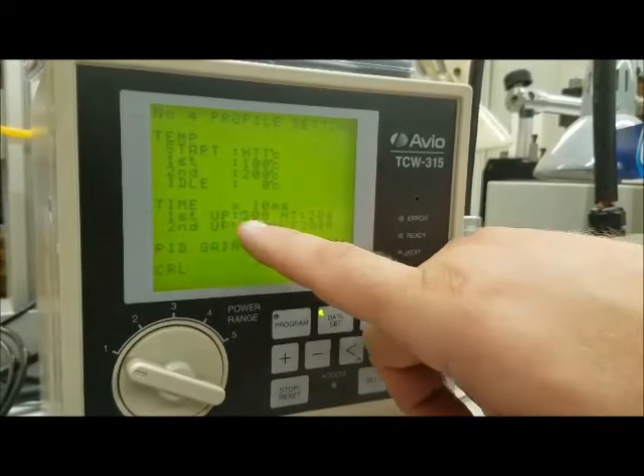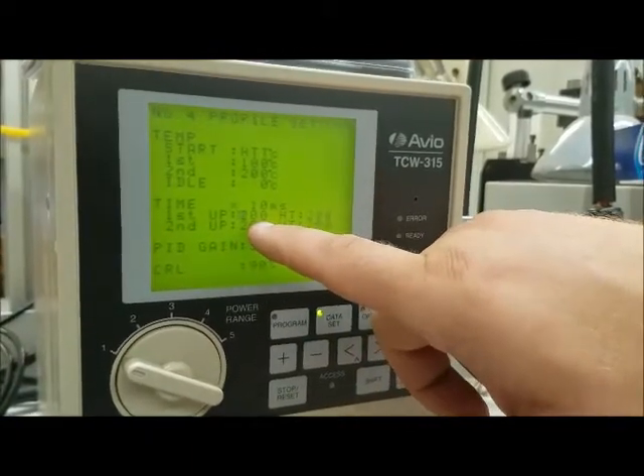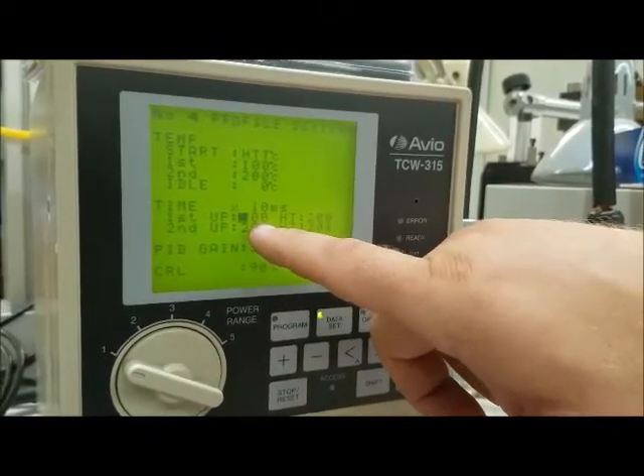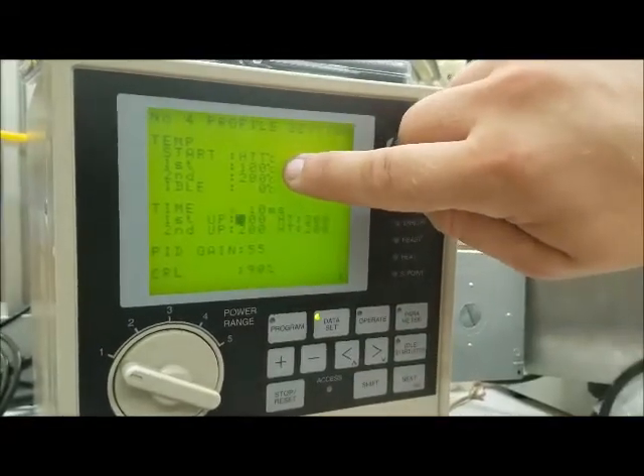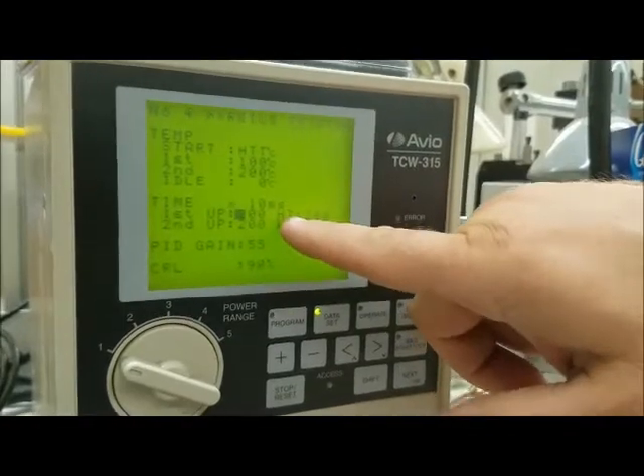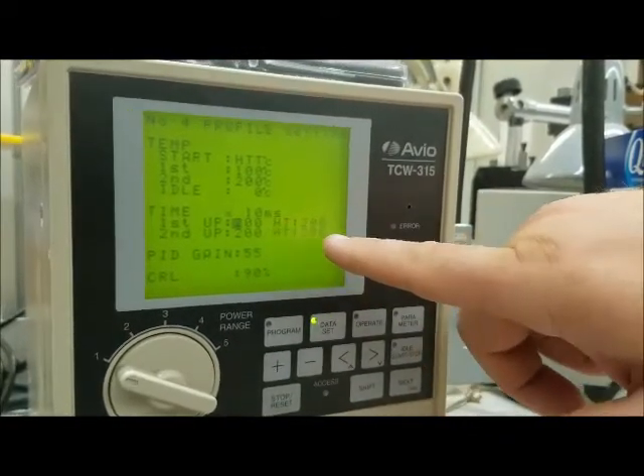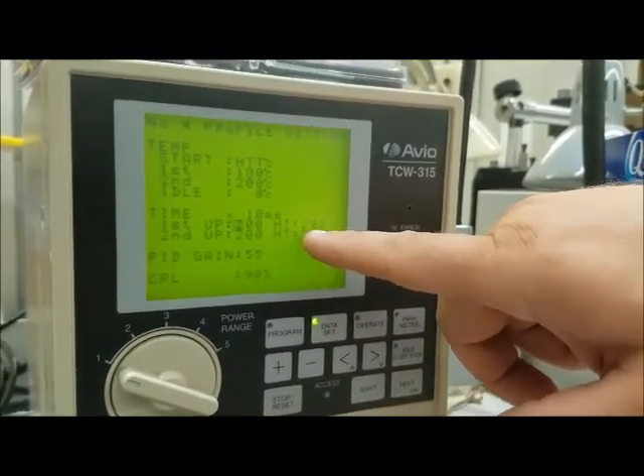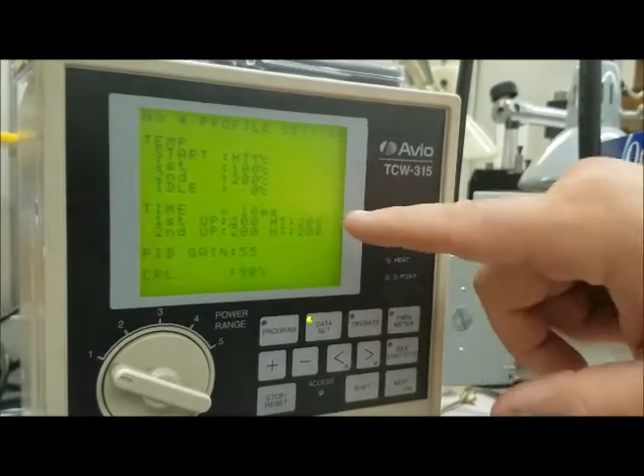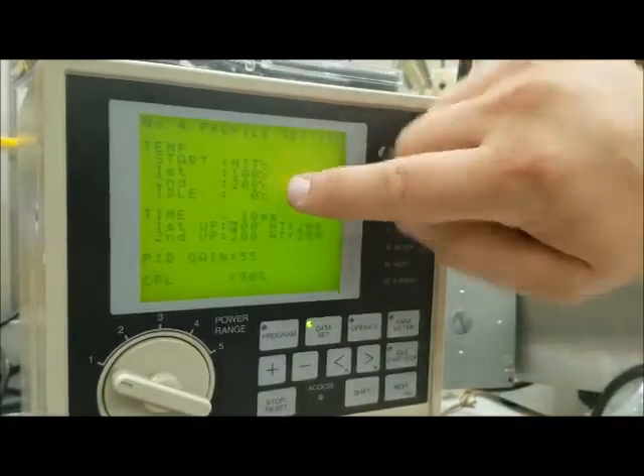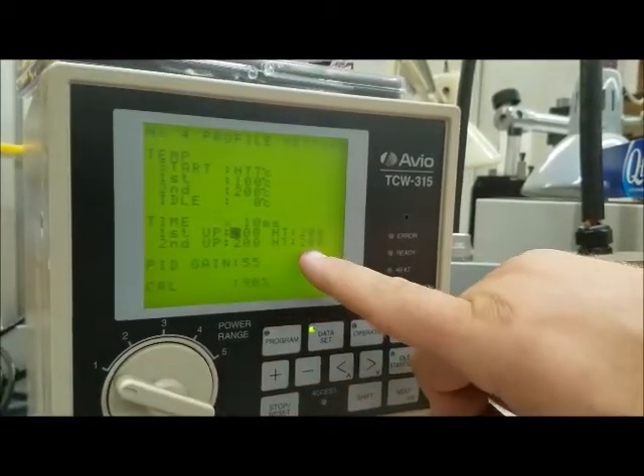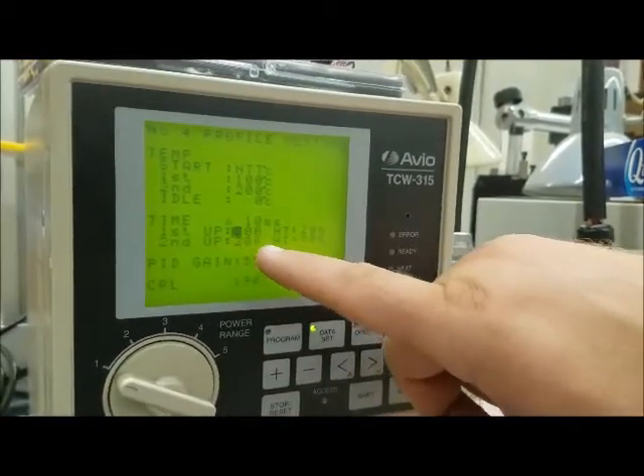First uptime is the ramp—how many seconds it takes to ramp from ambient temperature to the first hold temperature. HT stands for hold time, the time period it will hold at that first temperature. Under the second line, you have another ramp time and hold time. Again, these are in milliseconds times whatever that number is.